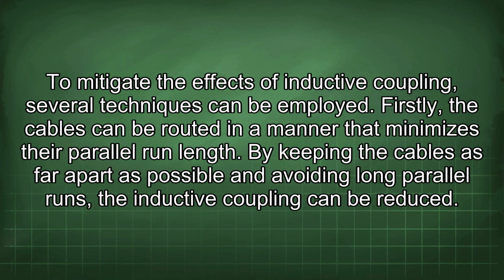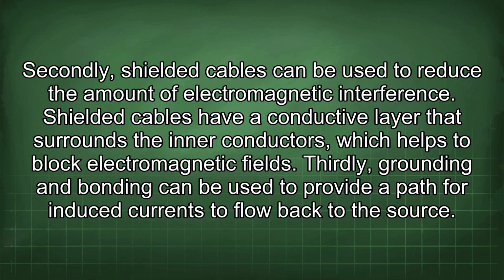To mitigate the effects of inductive coupling, several techniques can be employed. Firstly, the cables can be routed in a manner that minimizes their parallel run length. By keeping the cables as far apart as possible and avoiding long parallel runs, the inductive coupling can be reduced. Secondly, shielded cables can be used to reduce the amount of electromagnetic interference. Shielded cables have a conductive layer that surrounds the inner conductors, which helps to block electromagnetic fields.